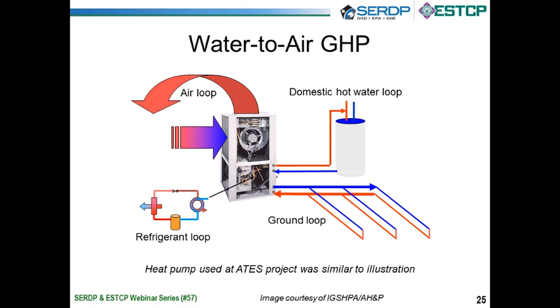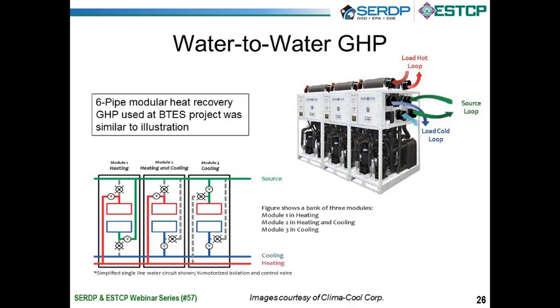In our situation, those boreholes go vertically down into the ground, and sometimes you do some domestic water heating also. So that would be a water-to-air heat pump. At the project in Albany, we had water-to-water. So in the upper right there is three modules. We happen to have five modules, each about a nominal 85 tons.